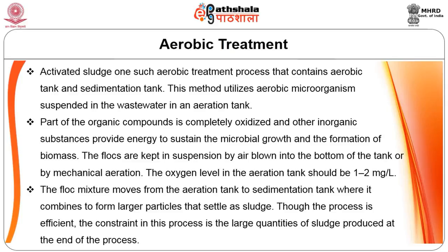Activated sludge is an aerobic treatment method containing an aerobic tank and a sedimentation tank. It utilizes aerobic microorganisms suspended in the wastewater in the aeration tank. A part of the organic component is completely oxidized and inorganic substances provide energy to sustain microbial growth and biomass formation. Flocs are kept in suspension by air blown into the bottom of the tank or by mechanical aeration; the oxygen level should be 1–2 mg/L. The floc mixture moves from the aeration tank to the sedimentation tank where it forms larger particles that settle as sludge. A constraint of this process is the large quantity of sludge produced.